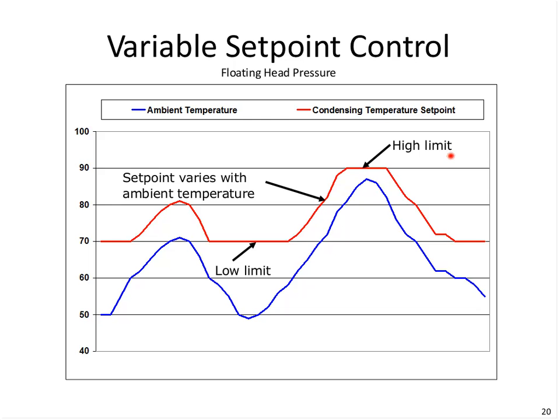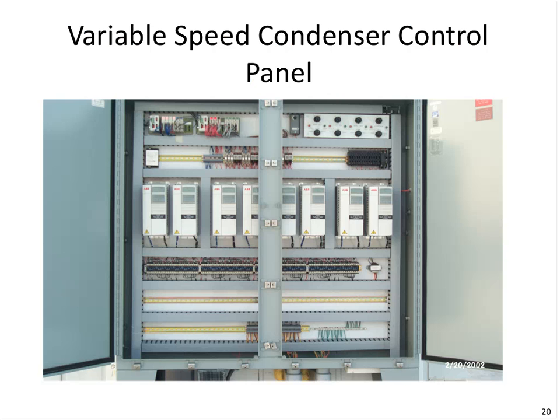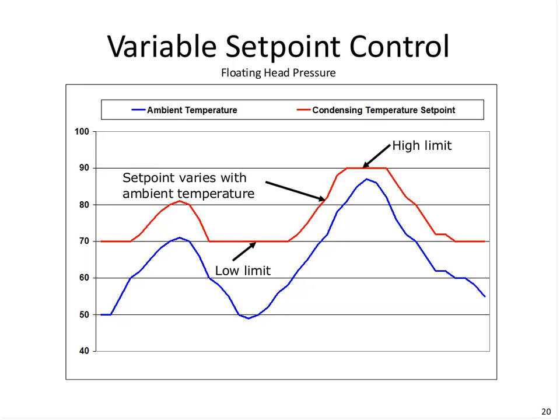If we're on variable frequency drives, notice in the panel here, our frequency drives would then be detecting the conditions where full speed is needed in order to maintain condensing temperature as best we can. And then as ambient drops off, we just follow it again. So this shows really the day in the life of, or 2 days in the life of, a variable set point control with floating head pressure.